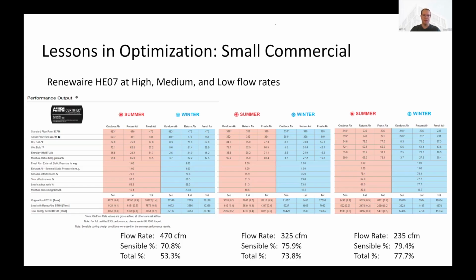So you may need or likely will need to rely on the manufacturer to put in the project data, what the temperature differences are inside and out, to actually calculate this information. And so anytime you have one of those larger ERVs, you're probably requiring a project-specific calculation based on some AHRI standard process. In this case, we have a flow rate of 470 CFM on the left, the high one, and the sensible recovery efficiency is 70.8. And if we did the total recovery efficiency, or moisture recovery, we are down at 53.3.